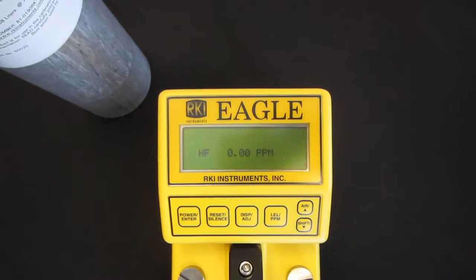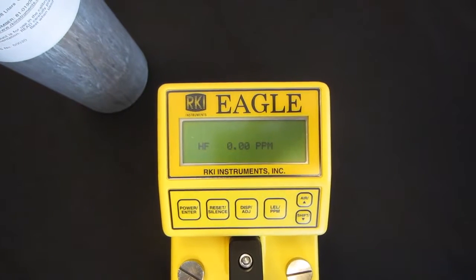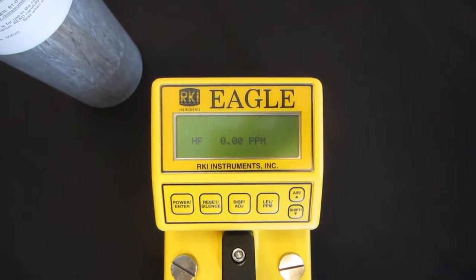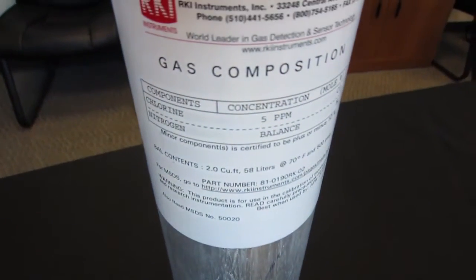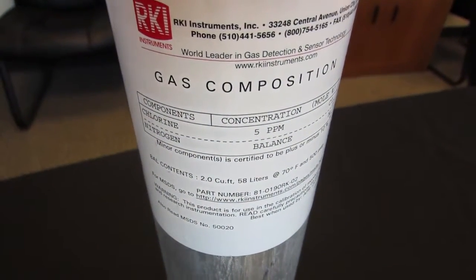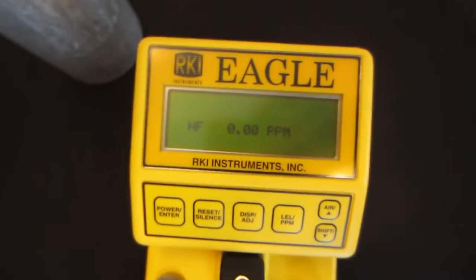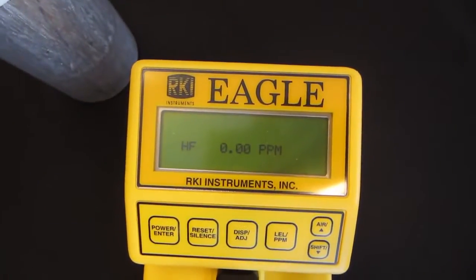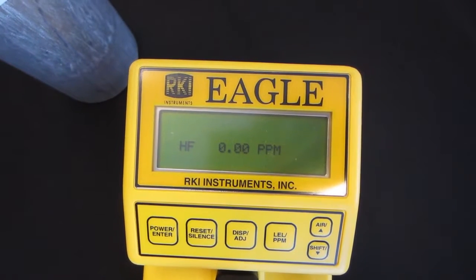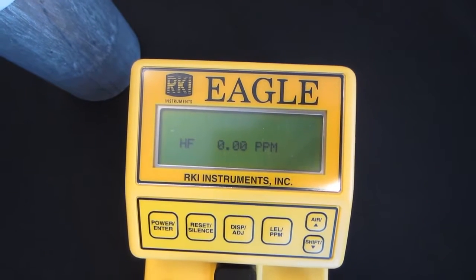Okay, now we're going to bump test the Eagle with an HF sensor using chlorine gas. We've already properly calibrated the Eagle to the chlorine cylinder, and that is because we can use chlorine as a substitute gas that's readily available. You really cannot get HF, hydrogen fluoride, in a disposable calibration cylinder, so chlorine is a very convenient substitute.